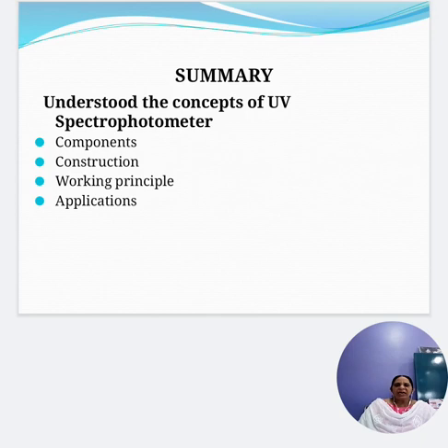The next component was the sample container. The sample cell holding the sample must be transparent to the wavelength that is to be recorded. So quartz or fused silica cuvettes are used for the ultraviolet region.